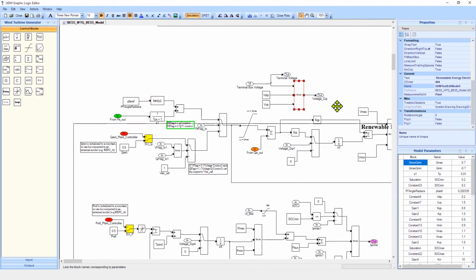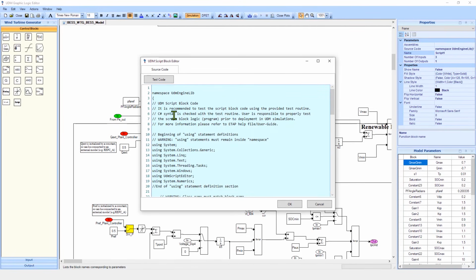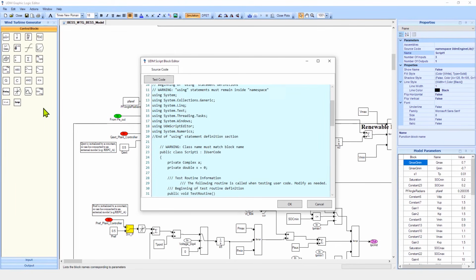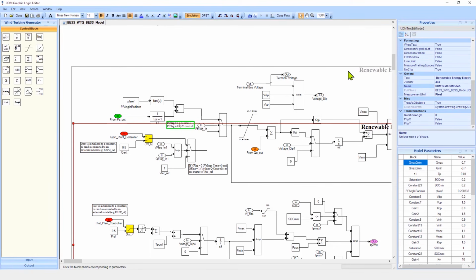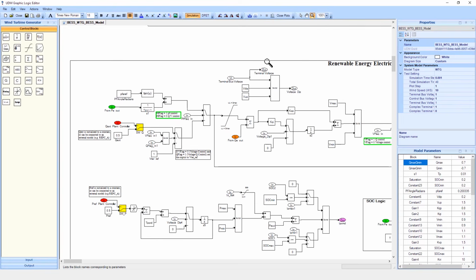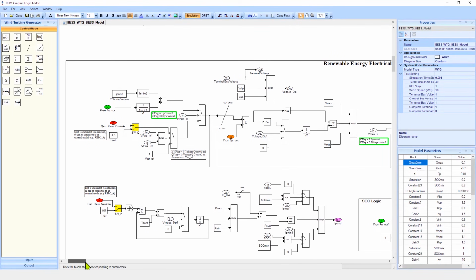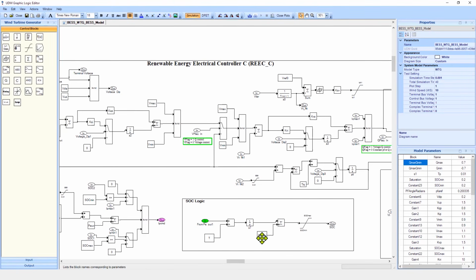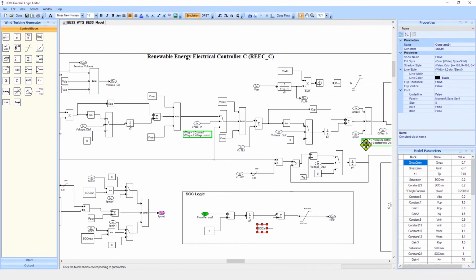For situations where the control blocks may be insufficient, you can also add a script block and use C# syntax to define any kind of logic that cannot be defined using these standard control blocks. Using UDM, we can build the complete battery energy storage system transfer function that not only includes the plant level controller, but also includes the state of charge logic. In this instance, we can see that the state of charge logic has already been defined. It includes certain variables such as the maximum and minimum state of charge, as well as some initial state of charge. Its output is then driven into an electrical controller, which is also defined, that includes various modes of operation such as voltage control, power factor control, reactive power control, and so on.